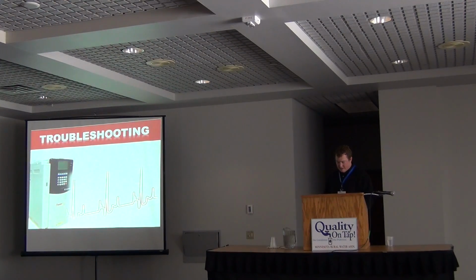All right, we're going to talk a little bit about troubleshooting. And the number one tip I have is don't troubleshoot the VFD. Troubleshoot the application. This is going to be a high-level troubleshooting approach, but it might give you something to think about. So ask yourself, have there been any reasons for power quality concerns? Meaning, did a storm just go by? Did the lights go out for a second? Did the generator kick on? What happened that caused this VFD to fail?